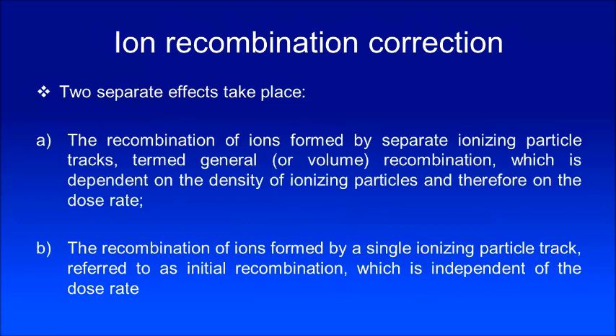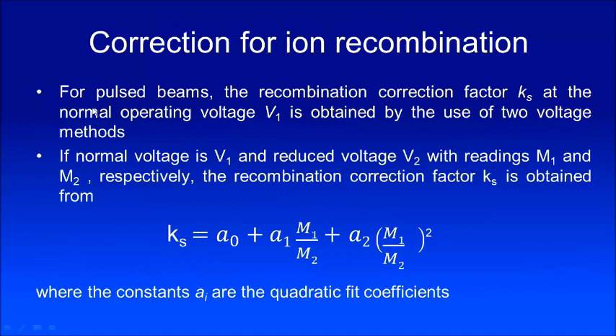Therefore we apply a correction for ion recombination. For pulsed beams, the recombination correction factor K_s at the nominal operating voltage V1 is obtained by the two-voltage method. V1 is the voltage at which your chamber was originally calibrated — say +300 V, giving meter reading M1. Then reduce the voltage to V2 — say 200 V — and get meter reading M2. Use the equation with quadratic fit coefficients A0, A1, A2 (provided in TRS-398 for various V1/V2 ratios) to get K_s. This equation applies to pulsed beams.